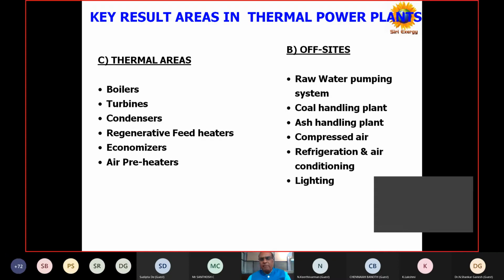In ash handling plant, again once the coal is burned, the ash is generated. It is a fly ash, it is a bottom ash. So those have to be separated out and, maybe sometimes we have to make it a slurry and send it out to the ash dike, far away place. And also fly ash nowadays people are selling to the cement plants. So for that we have to make arrangement for transport, the dry ash transport through a compressed air system. Then compressed air is used as a process air, also as an instrument air, and also, as I said, for the ash handling.